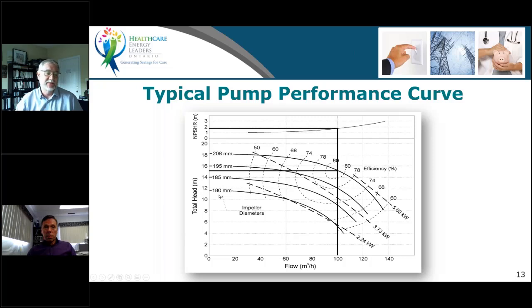And in fact, if we change impellers in a pump, we can basically make it into a different pump. So a lot of times people say, well, I need a smaller pump. Well, no, maybe you just need a smaller impeller to achieve the lower flow, with a smaller diameter impeller. So whether it's the speed of the pump or the diameter of the impeller, that's a very similar relationship. But ultimately, as we change that pump, we end up with different operating efficiencies.